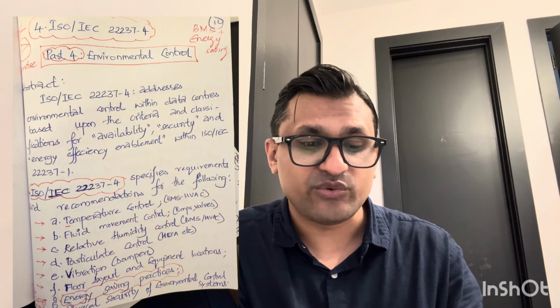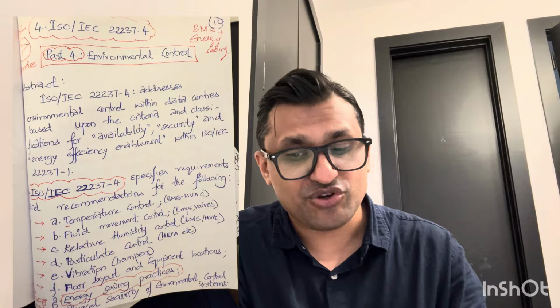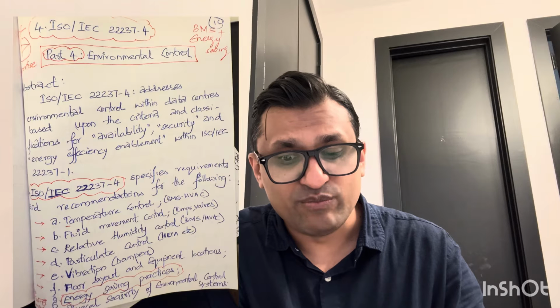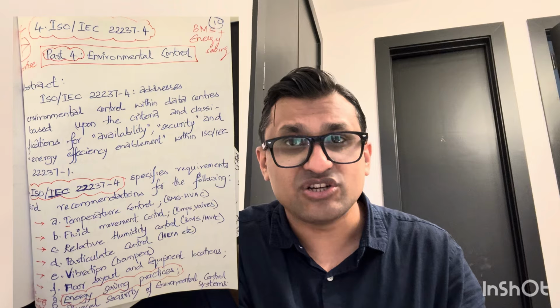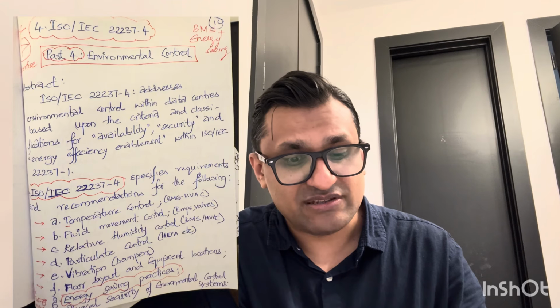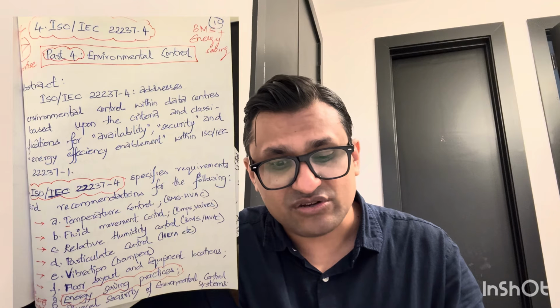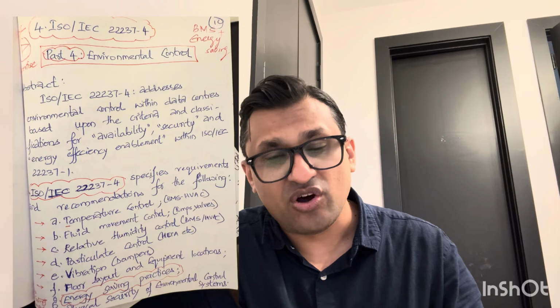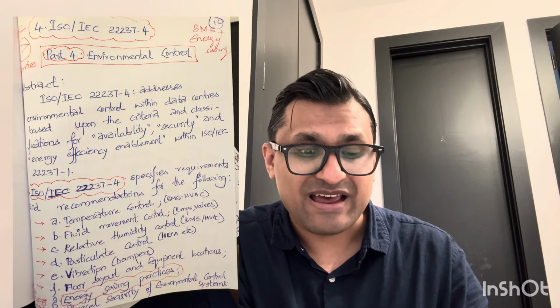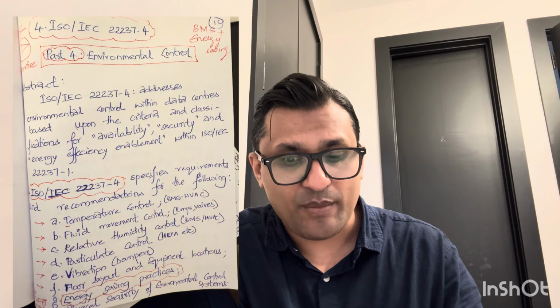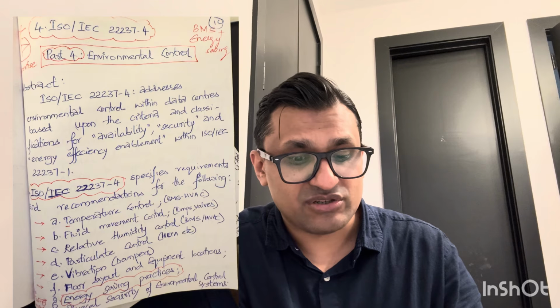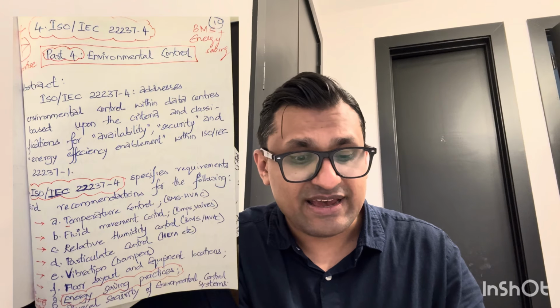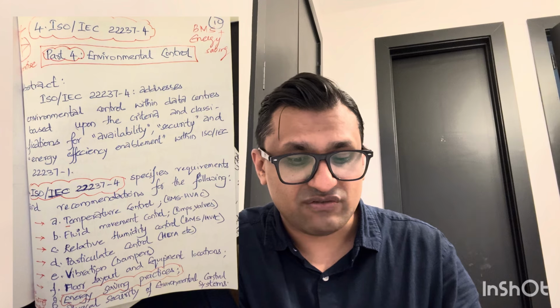ISO 22237-4 specifies requirements and recommendations for: temperature control (BMS, HVAC); fluid movement control, pumps and valves; relative humidity control (BMS, HVAC); particulate control, such as HEPA filters to ensure dust, debris, or particulates don't enter the more sterile environments in the data center; vibration dampers; floor layout and equipment locations; energy saving practices; and physical security of environmental control systems. That's what part 4 specifies.